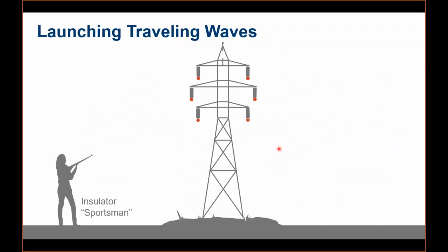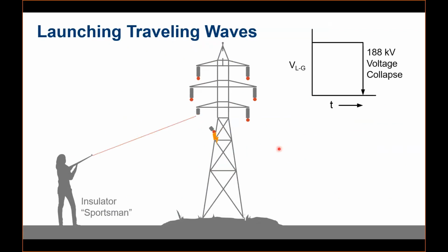Okay, how it works, just to have a concept: just as we drop the pebble in water, similarly, suppose you have an insulation failure, where an insulator has been broken due to aging or some external factor, so it may touch the ground. This is a very simple example: one phase's insulation has broken down and touched the ground. So we have a change in the voltage, or a disturbance. We can consider it as a phase to ground voltage. From its peak, it went to the ground immediately. Just consider it a bolted fault.